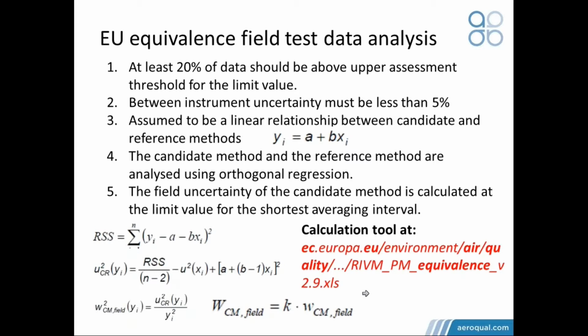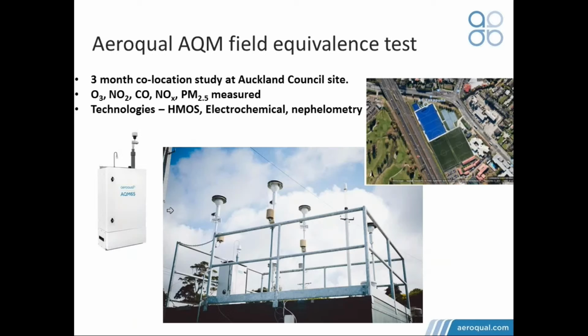So the field test program is to take the sensor instruments, co-locate them with a reference station, and then to collect hourly data, typically hourly data, but for dust it would be daily average data, and put the data into the spreadsheet, and it calculates the standard relative uncertainty according to a particular limit value. So you can enter in a particular limit value for the criteria pollutant you're looking for. So for ozone, for example, you might put in 100 ppb as the limit value, but you have the choice of selecting that. So I just want to run through an example of an equivalence test for one instrument.